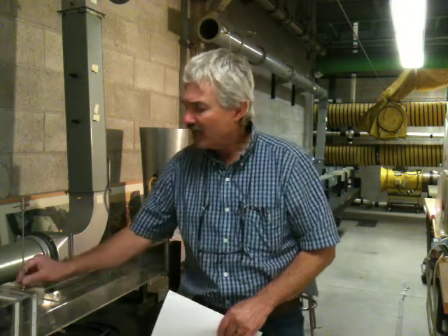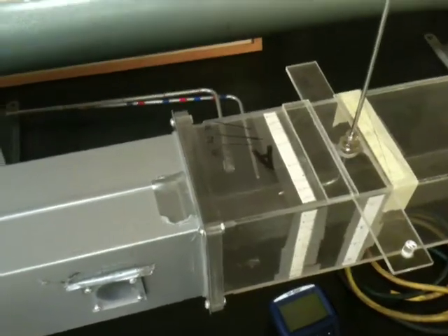You'll take a look at the uniformity or non-uniformity of the distribution. And then also we'll take an average velocity for the whole airway, and we'll calculate a correction factor that we will apply to just the centerline velocity. And we're going to use that for the rest of the exercises throughout the lab session. Then we've also got some angled marks, which you can see right here. And we're just going to use those to study the effect of misalignment on the velocity pressure readings.